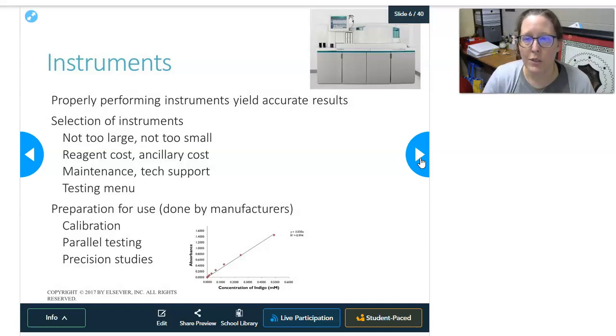But you also have to make sure that the instrument that has been selected is appropriate for the lab. So it's kind of like the Goldilocks principle, not too large, not too small. It can do the right amount of work for your work volume, the volume that your lab handles. Some labs that have really, really high volume may have multiple chemistry analyzers to handle their volumes. But if you have a lower volume lab, then you may not need one of those big floor models. You might go with a smaller benchtop model.